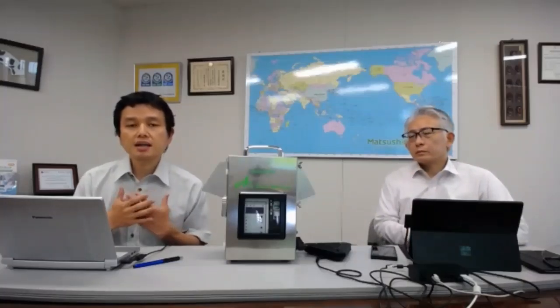When the sensor has a malfunction and the transducer outputs a fault alarm signal, it's because the CPU of the air dust monitor has a self-diagnosis function that outputs the fault alarm. If the sensor itself is sent back to our plant, we also have a calibration service at our factory. Some of our regular customers request calibration at the factory every one or two years.